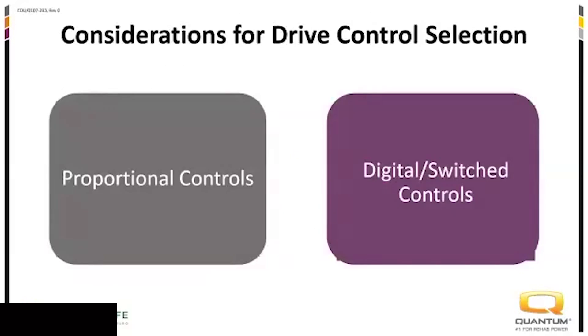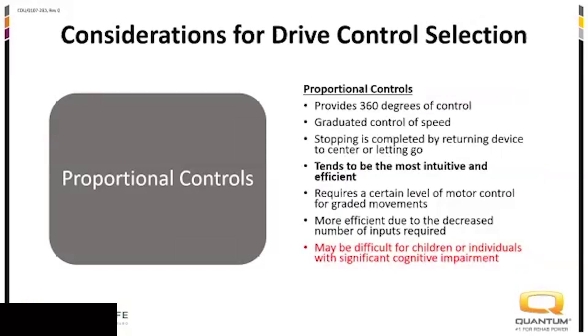When we start thinking about drive controls, there are really two different types: proportional devices and switch devices. With proportional devices, the more input you give, the more output you get — essentially like a gas pedal or plane throttle. That's what a proportional device is.